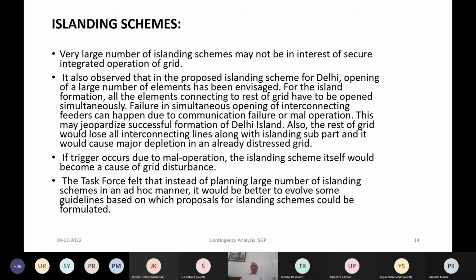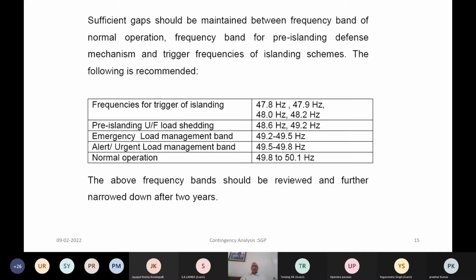And for the island formation, all the elements connecting to the rest of the grid have to be opened simultaneously. Failure in simultaneous opening of the interconnecting feeders can happen due to a number of reasons, including failure of the communication or undesirable opening, and this may jeopardize the success of the island to survive post initiation. Another thing which happens is, within the island there would be generation and load imbalance, and the island may not survive. So these are some of the concerns which need to be addressed when the islanding schemes are planned.